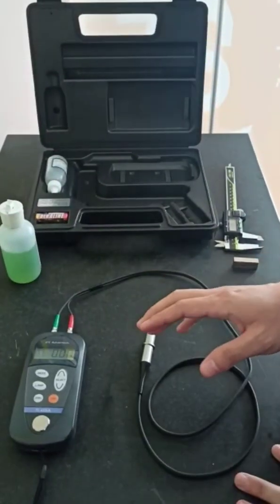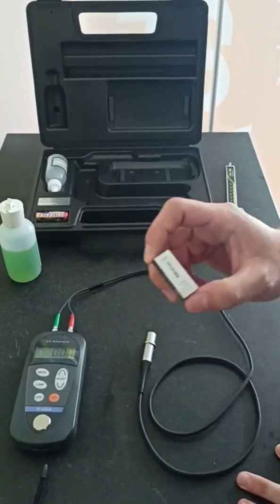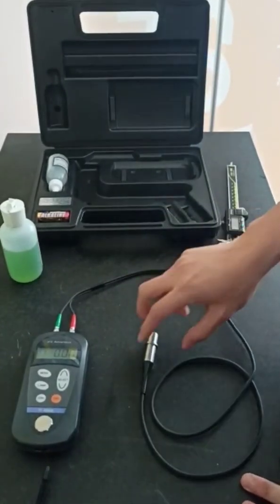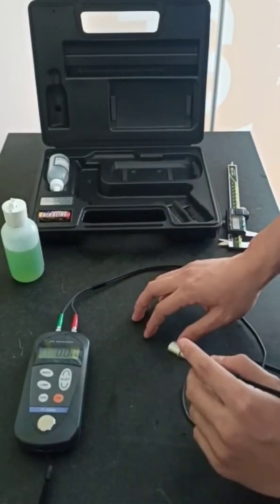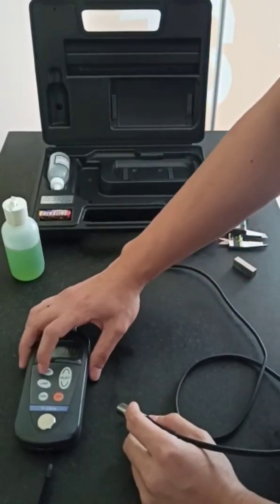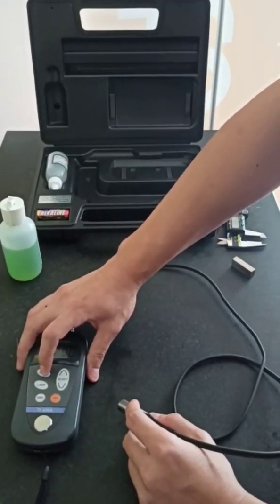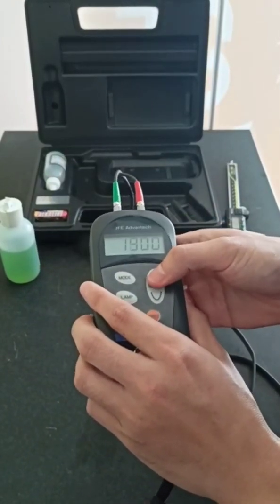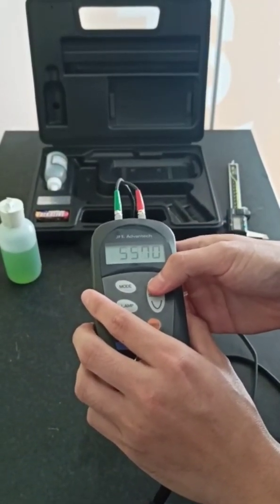First, let me show you how to measure a steel material, specifically a steel gauge block. Before taking any measurements, we need to do the zero setting for the steel material. In the mode settings, we need to set the relevant acoustic velocity, which for steel is 5920.